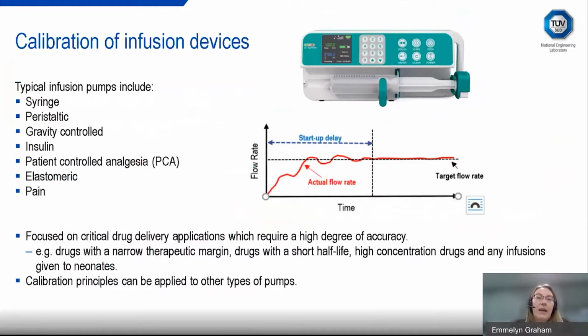So when we talk about calibration of infusion devices, what I have at the very top of the screen is an example of what a syringe pump looks like. So you've got your plastic syringe and then you can program in the actual flow rates that the syringe should deliver. The graph shows if you start up the flow rate, it'll take a while and there will be a delayed startup time until you achieve your actual flow rate. So this is what we're looking at when we're doing calibrations, how quickly it gets to the target flow rate and how stable it is.